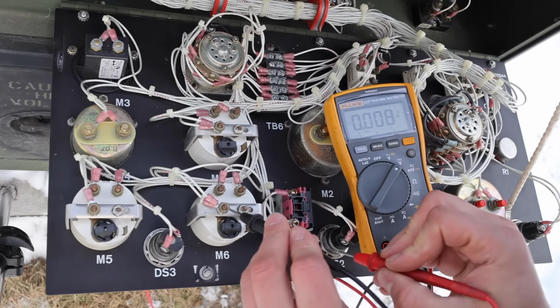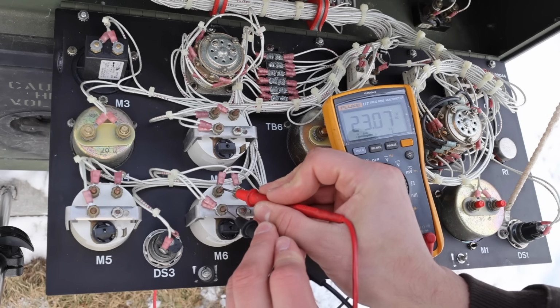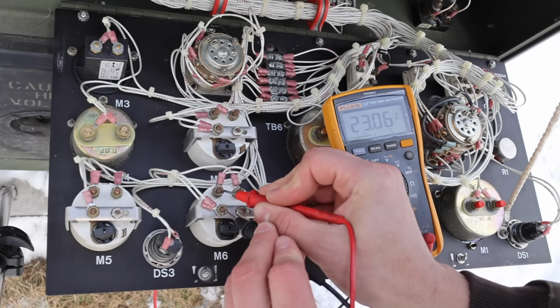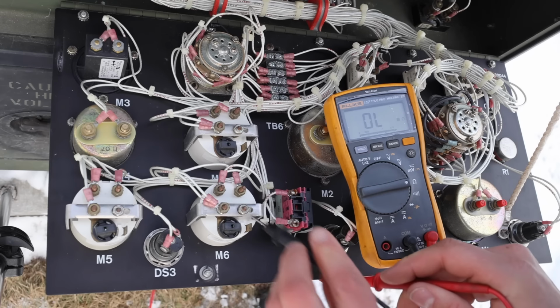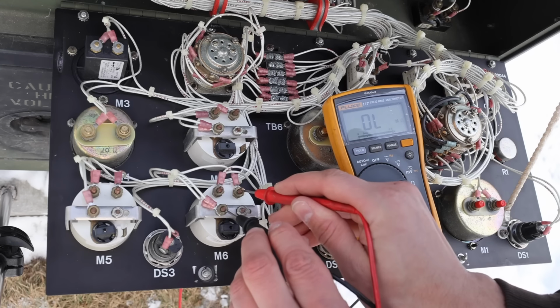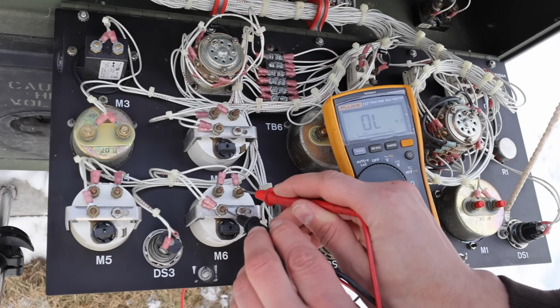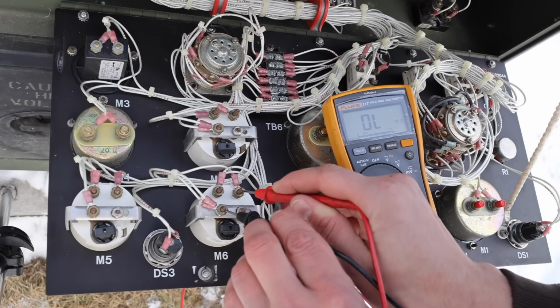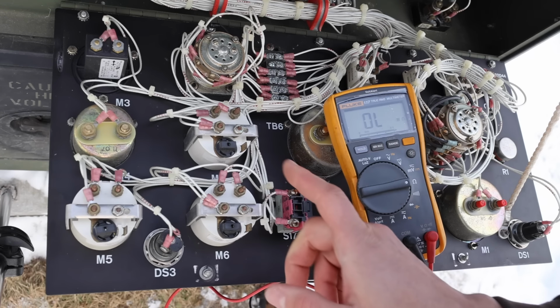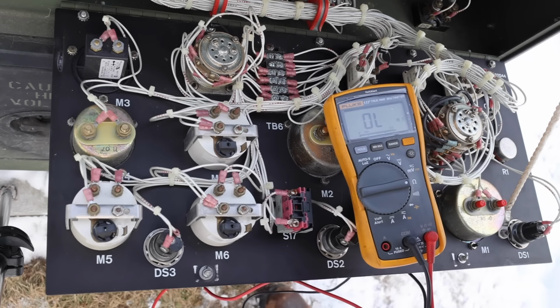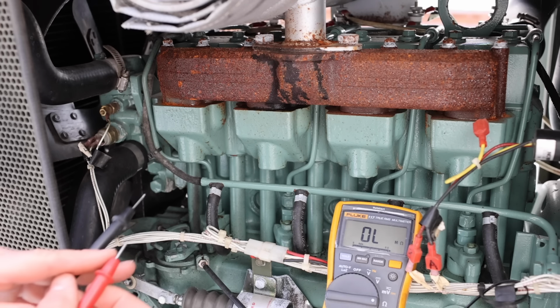First I'm going to check ground and power, and we're getting 23 volts. That's good enough. Second, I'm going to check the resistance from the ground to the sensor, and I'm not getting any resistance. That's a problem. I should be getting some resistance there, so that's telling me there's no signal coming into the gauge.